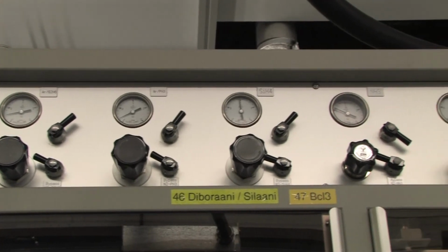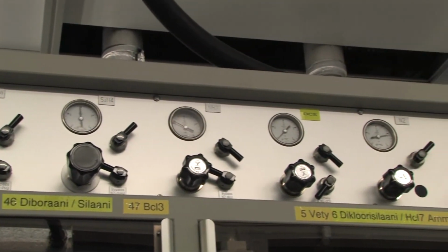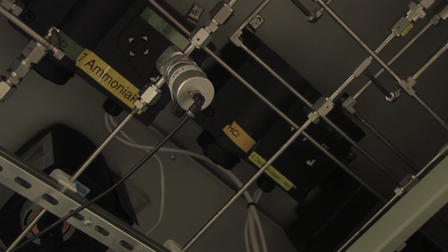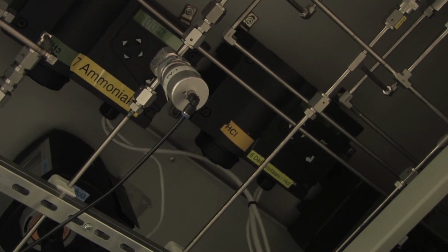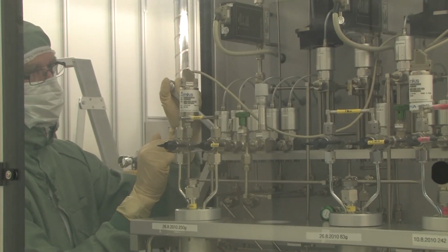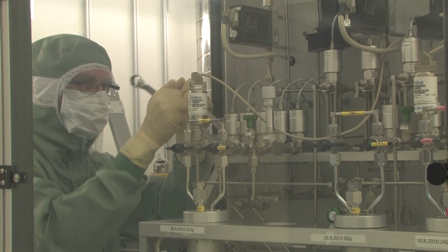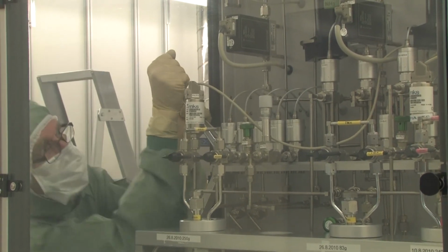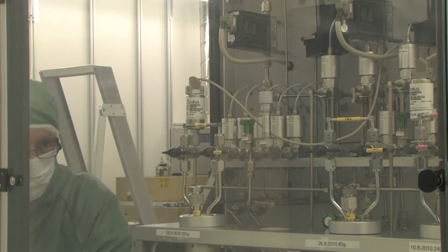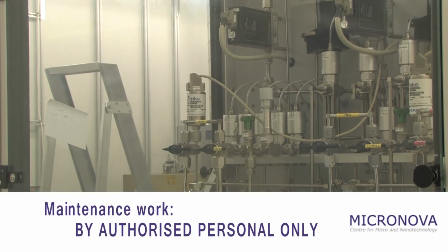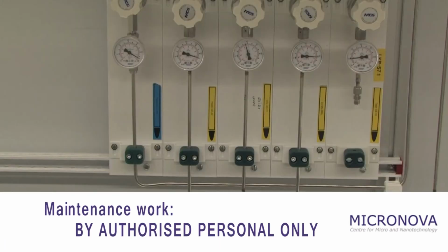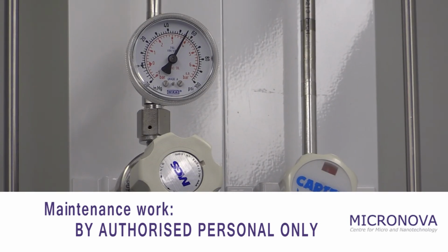Many process tools use dangerous gases or chemicals such as hydrogen chloride, silane, phosphine, and arsine. Incorrect maintenance operations can cause dangerous chemicals to be released into the air, for example while replacing parts connected to the gas lines. For this reason, maintenance work on gas and chemical systems is only to be carried out by persons authorised to perform these tasks.